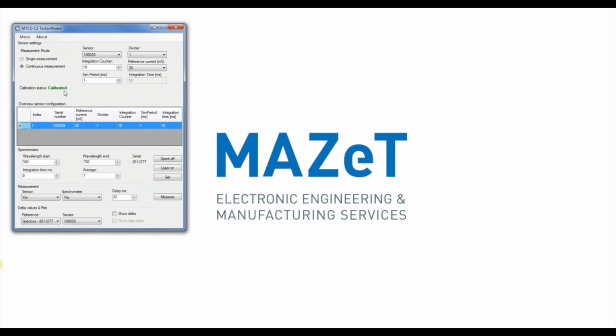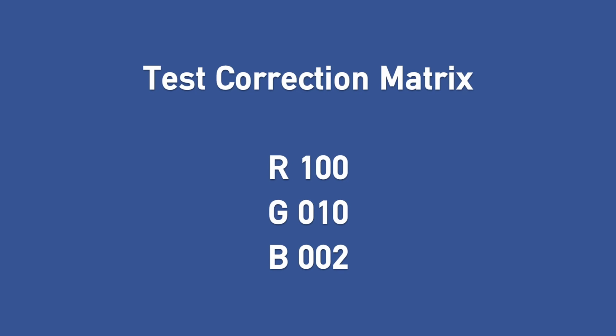Changing elements, such as integration time or reference current, requires a new calibration. If you don't have a spectrometer or reference values at hand, you can use a correction matrix that looks like this.